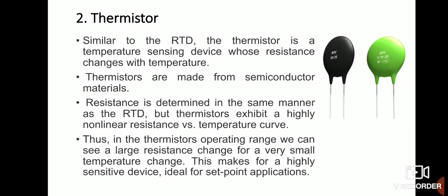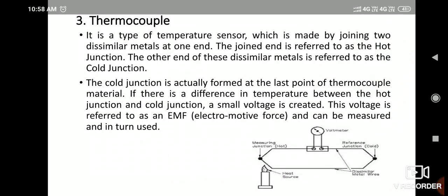Thermistors are made from semiconducting materials. Resistance is determined in the same manner as the RTD by connecting in the circuit. However, the thermistor exhibits a highly nonlinear resistance versus temperature curve. Within the thermistor's operating range, there is a larger resistance change for a very small temperature change, making it a highly sensitive device, ideally suited for set-point applications.